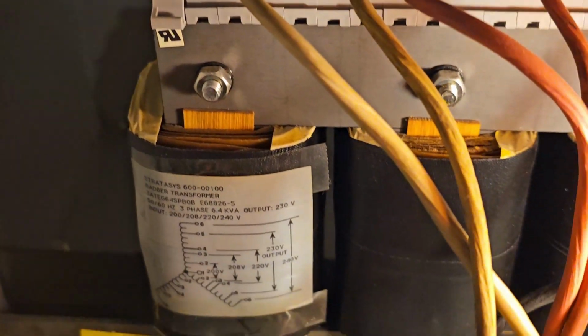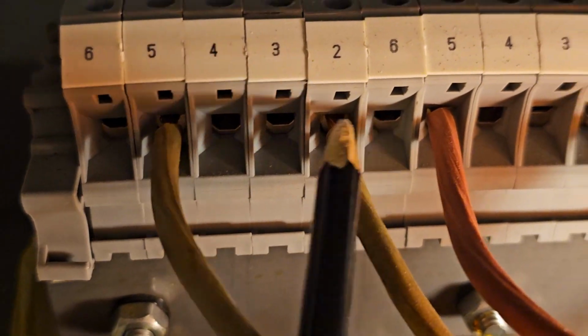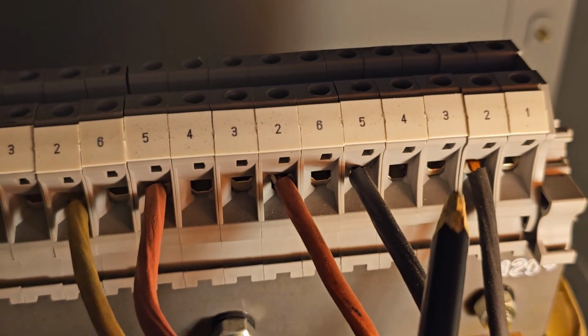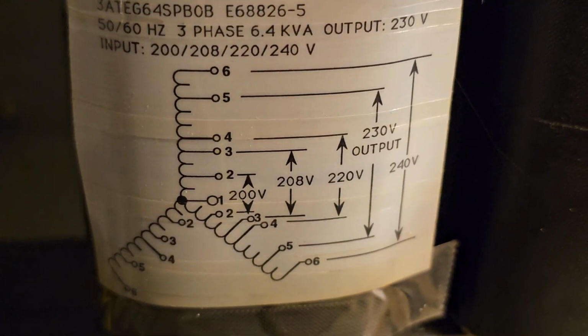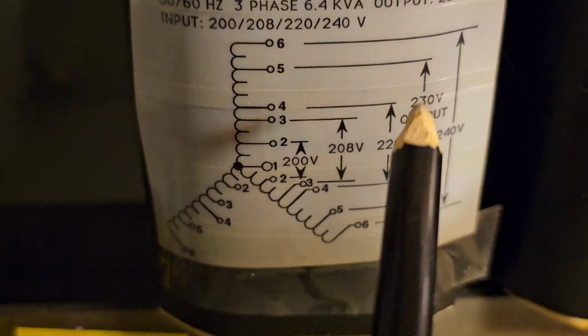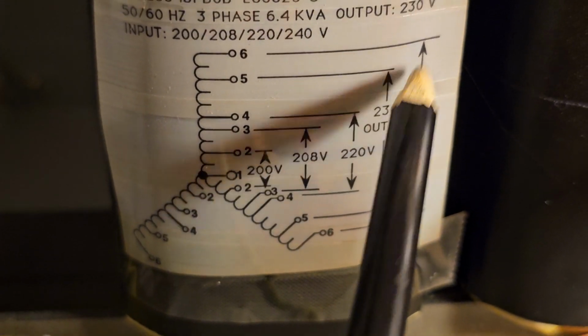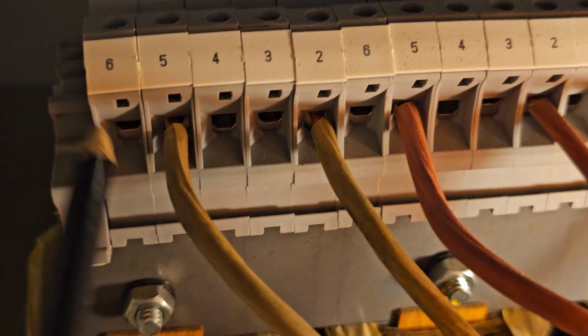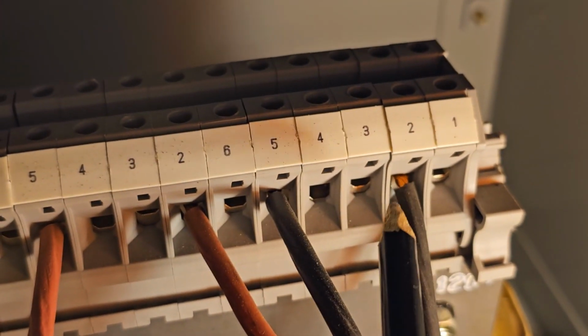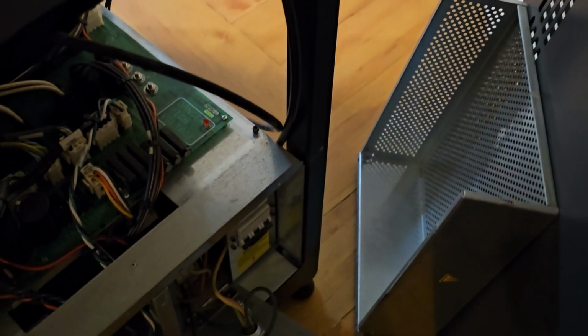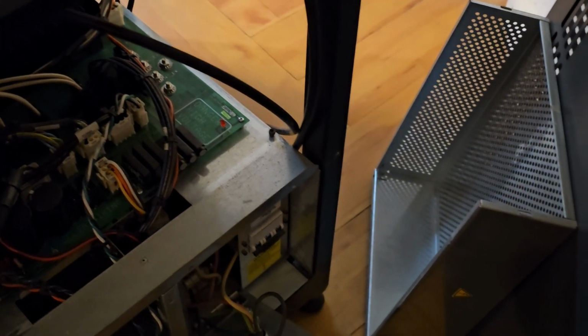I need to take these wires that are connected to number 2 - the white, the red, and the black - and instead move those to terminal number 6. You can see right here, the 240 volt input goes to terminal 6. So if I move these wires from number 2 to number 6, for all three, I should get an output now of 230 volts, not 300 and some volts. That's what I have to do today.